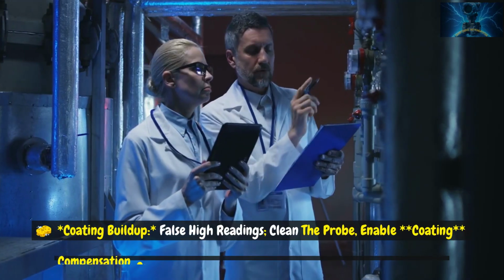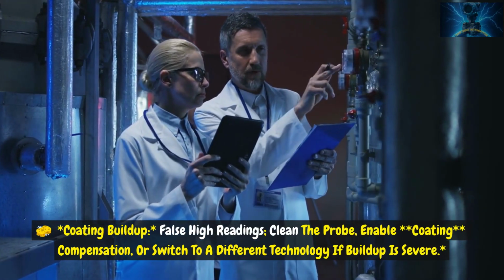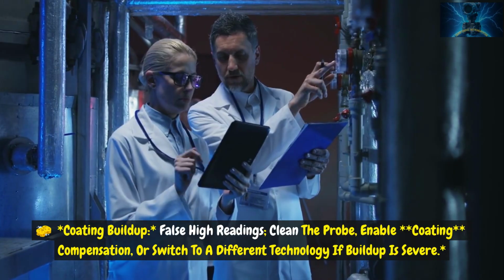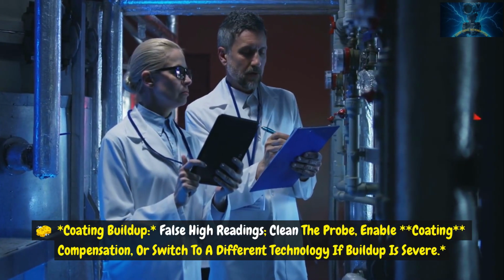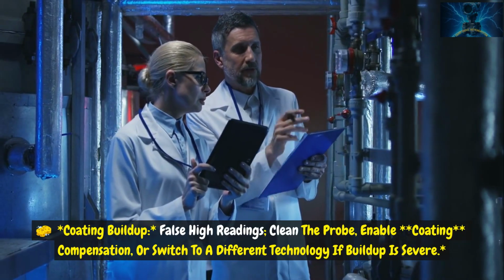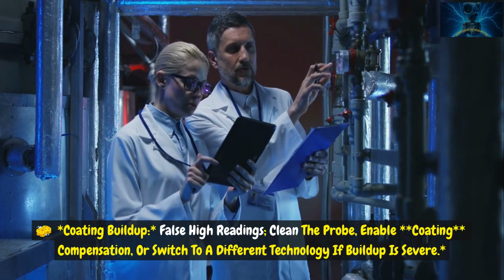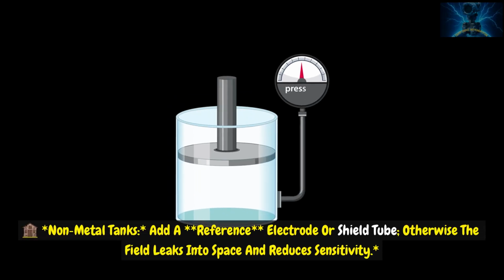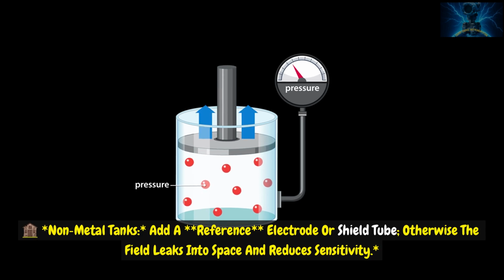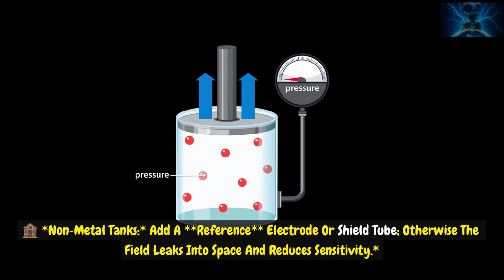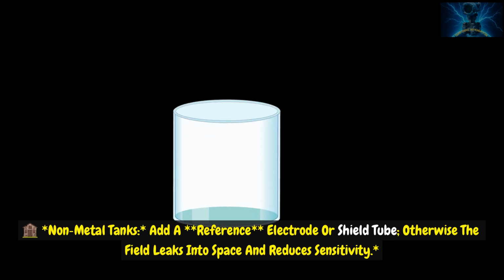Coating buildup, false high readings: clean the probe, enable coating compensation, or switch to a different technology if buildup is severe. Non-metal tanks: add a reference electrode or shield tube. Otherwise, the field leaks into space and reduces sensitivity.